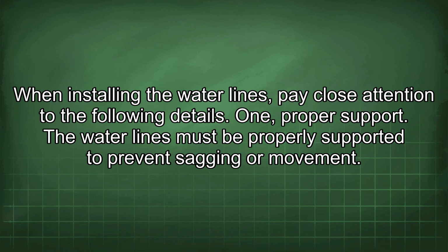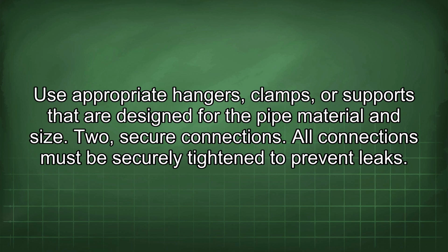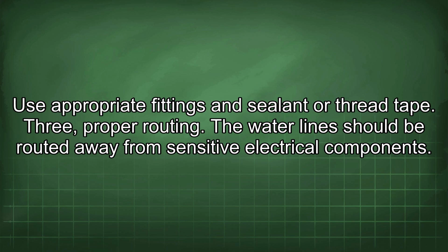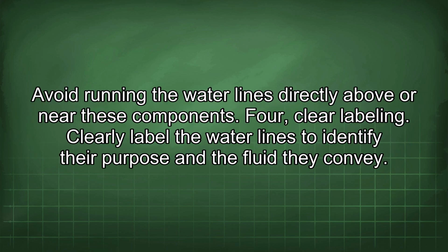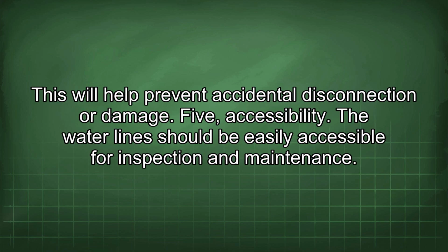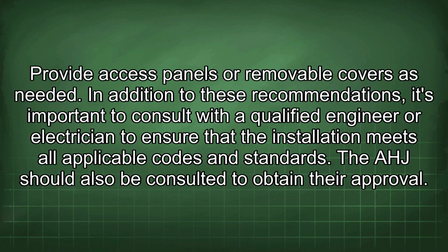When installing the water lines, pay close attention to the following details. 1. Proper support. The water lines must be properly supported to prevent sagging or movement. Use appropriate hangers, clamps, or supports that are designed for the pipe material and size. 2. Secure connections. All connections must be securely tightened to prevent leaks. Use appropriate fittings and sealant or thread tape. 3. Proper routing. The water line should be routed away from sensitive electrical components. Avoid running the water lines directly above or near these components. 4. Clear labeling. Clearly label the water lines to identify their purpose and the fluid they convey. This will help prevent accidental disconnection or damage. 5. Accessibility. The water line should be easily accessible for inspection and maintenance. Provide access panels or removable covers as needed.